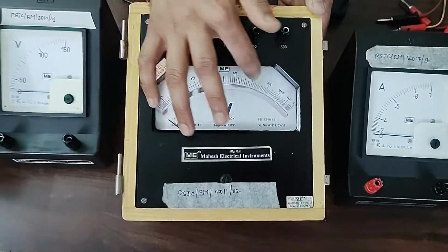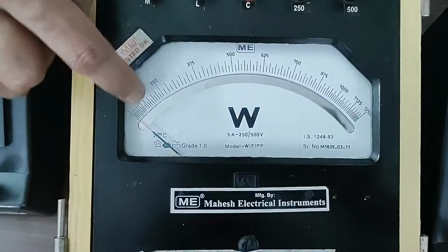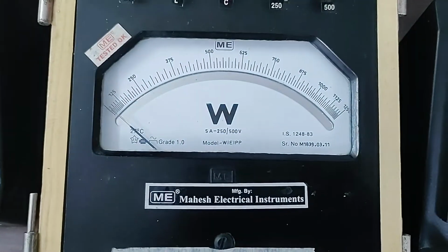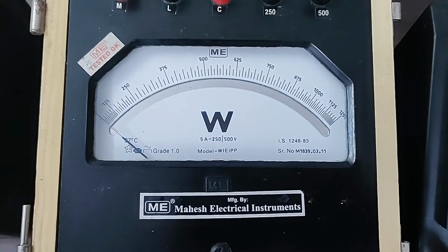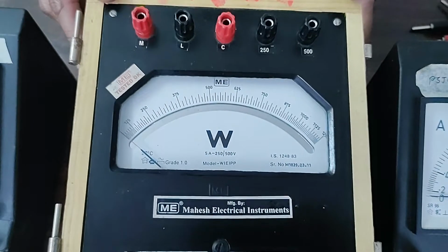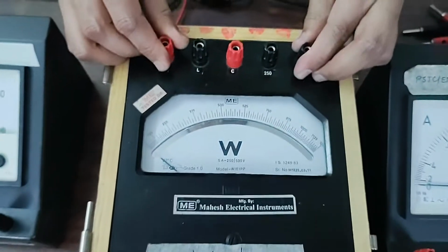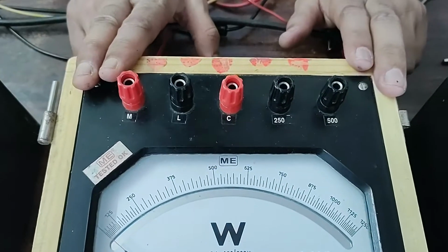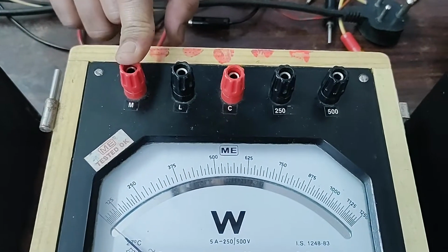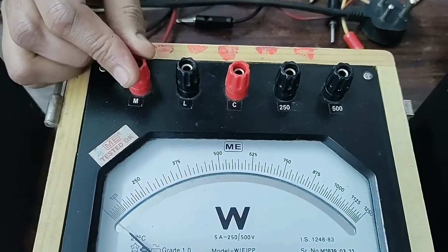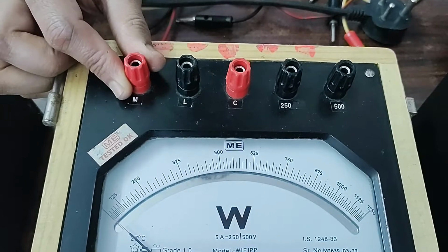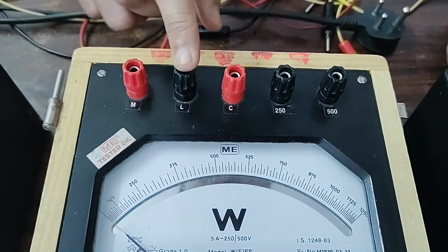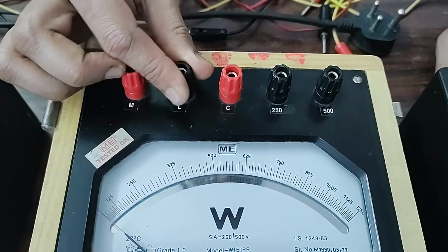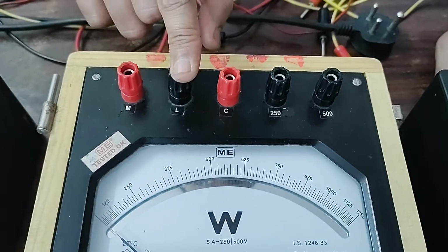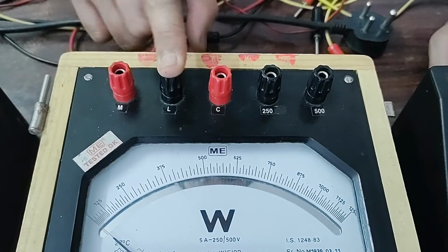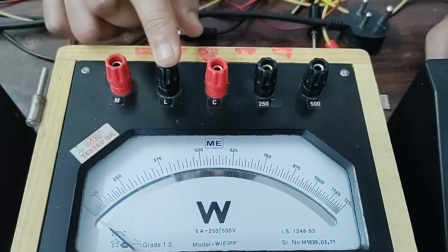We can see a scale here. The deflection of the pointer on this scale will indicate the power consumed in the circuit. That will directly indicate the wattage or power consumed. And these are the connecting terminals for connecting the wattmeter in the circuit. This first terminal, M, indicates the mains terminal, which we have to connect to the phase incoming wire. The second terminal, indicated by L, is the load terminal. So L we have to connect to the load, which means we connect phase here, and from here we take the wire towards the load.